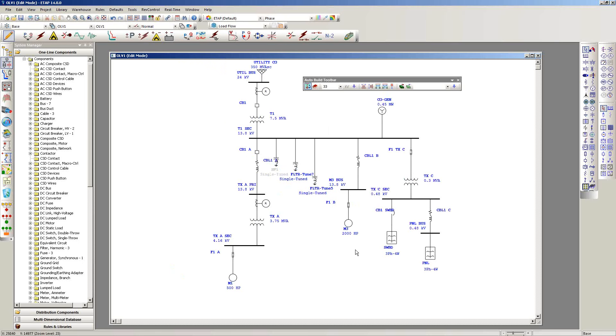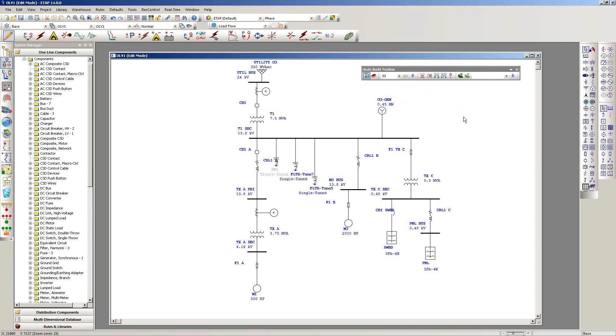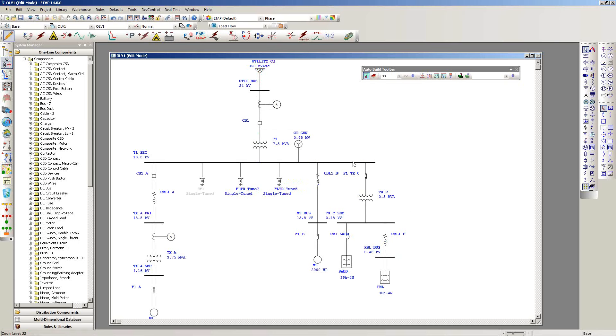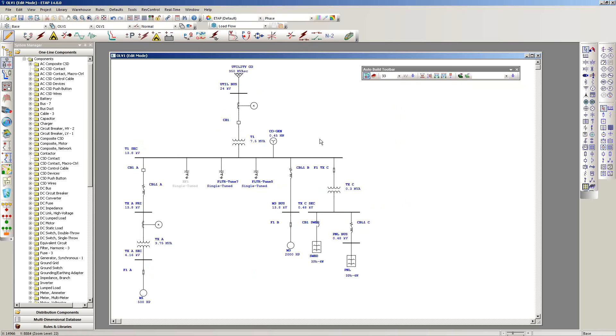For example, to fix the branch from a transformer feeding panel loads, select the two-winding transformer and click 'Fix Downstream Alignment' — the horizontal and vertical alignment is automatically corrected. Similarly, to fix another branch, select the topmost element such as a cable, click 'Fix Downstream Alignment,' and it's done. For a model with completely poor alignment, go all the way up to the utility element, click 'Fix Downstream Alignment,' and the entire one-line diagram is aligned based on the ETAP 14 rule book.